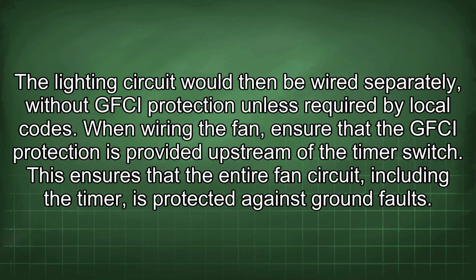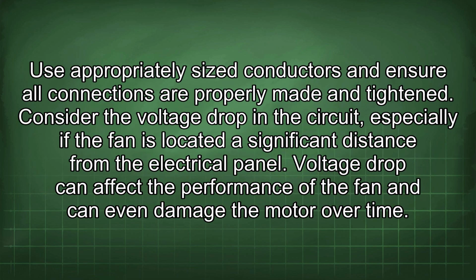When wiring the fan, ensure that the GFCI protection is provided upstream of the timer switch. This ensures that the entire fan circuit, including the timer, is protected against ground faults. Use appropriately sized conductors and ensure all connections are properly made and tightened.